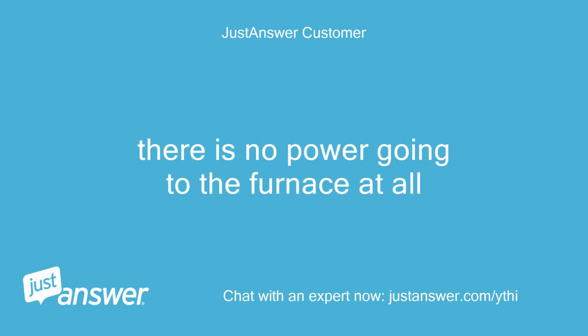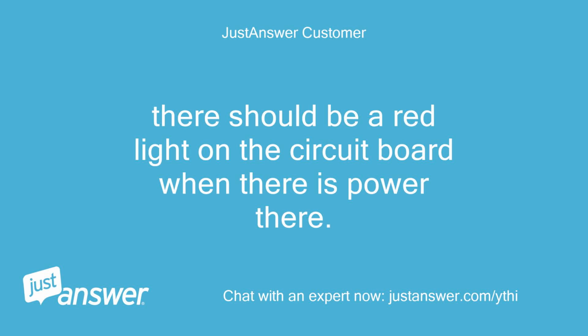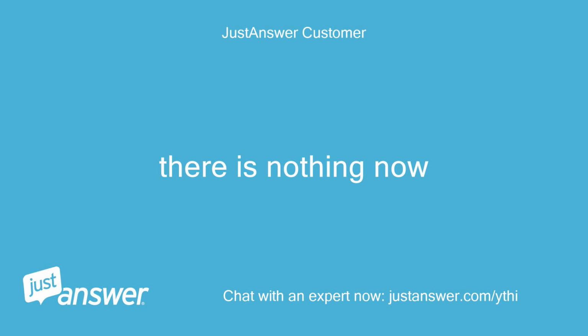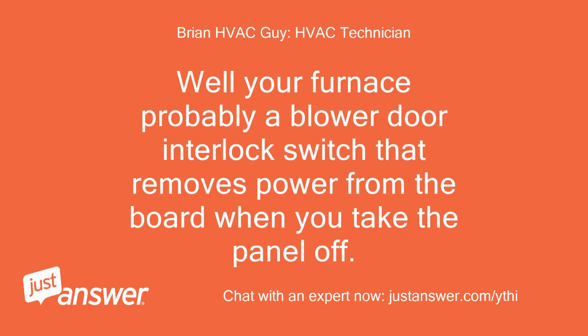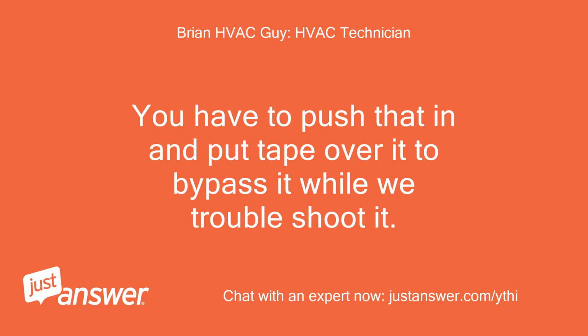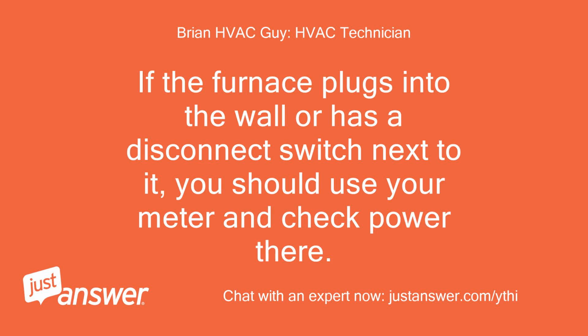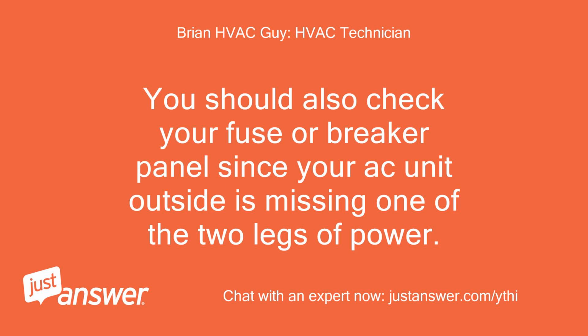There is no power going to the furnace at all. There should be a red light on the circuit board when there is power there. There is nothing now. Well, your furnace probably has a blower door interlock switch that removes power from the board when you take the panel off. You have to push that in and put tape over it to bypass it while we troubleshoot. If the furnace plugs into the wall or has a disconnect switch next to it, you should use your meter and check power there. You should also check your fuse or breaker panel since your AC unit outside is missing one of the two legs of power.